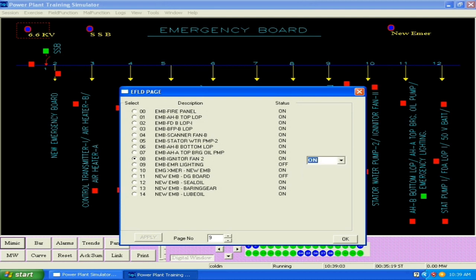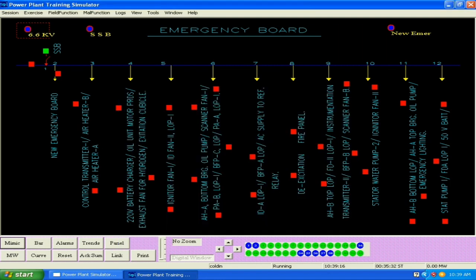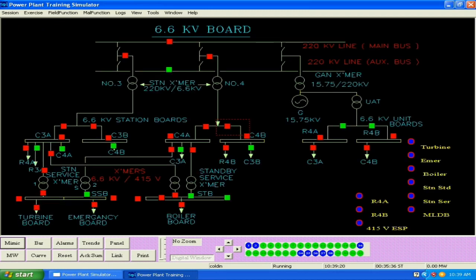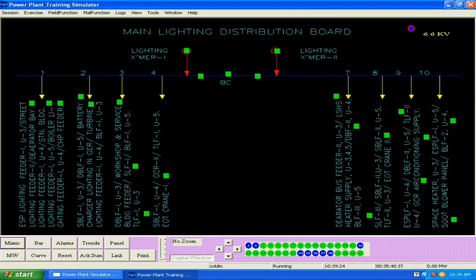The top LOPs, scanner fan, igniter fan and scanner fan, all these supplies are there on this board, emergency board. So the supplies are to be extended up to that point so that we can operate them, or in emergency, they can start automatically. So you have to make the supplies on, keep the supplies on.